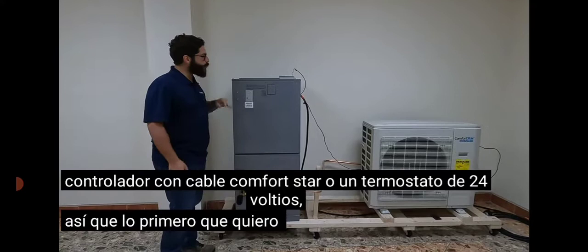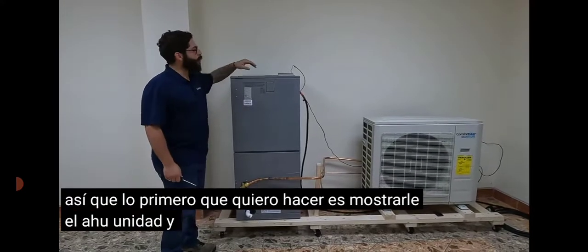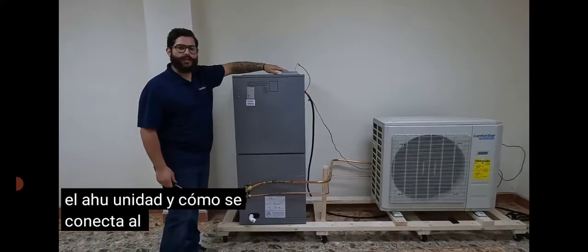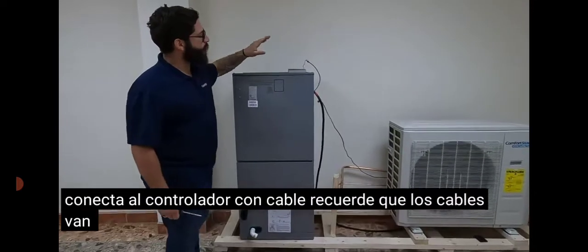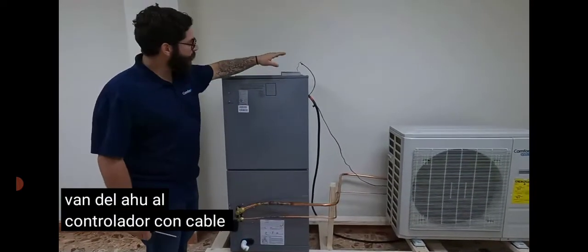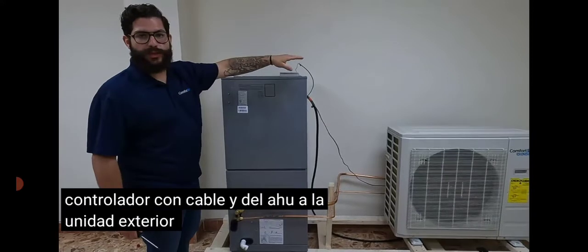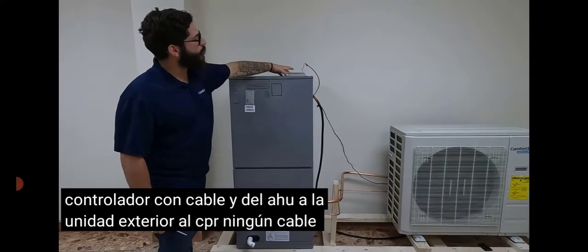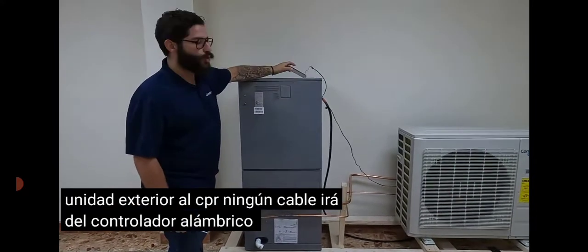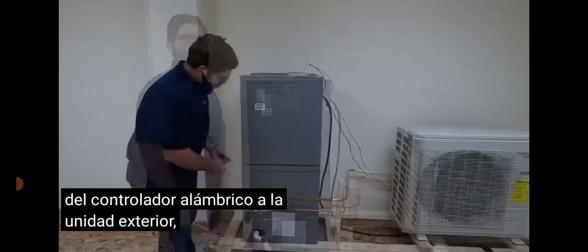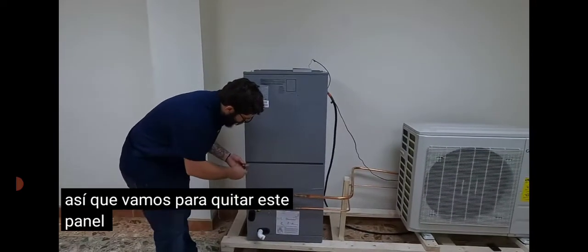First I want to show you the AHU unit and how it wires up to the wired controller. Remember, the wires go from the AHU to the wired controller and from the AHU to the outdoor unit, the CPR. No wires will go from the wired controller to the outdoor unit. So we're going to take off this top panel here.